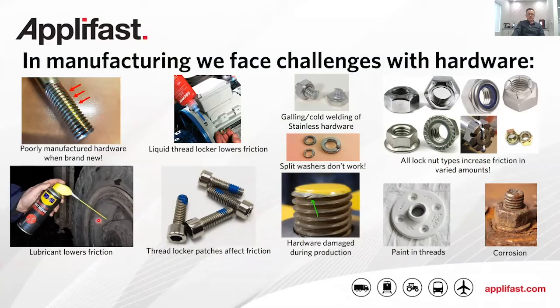Any lubricant, Loctite, or thread locker will decrease friction during tightening, which changes the effect. We know that stainless steel hardware has galling issues. Split lock washers do not work, that's been proven many times. Deformed thread lock nuts pack the plating into the threads, and prevailing torque increases while we fasten, which changes the dynamics as well.